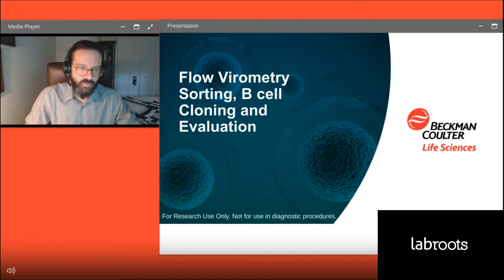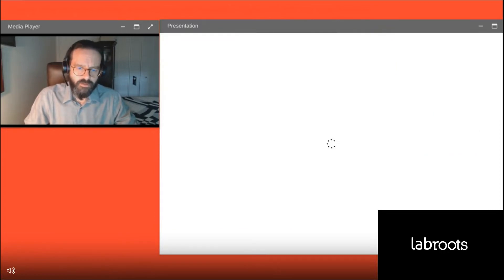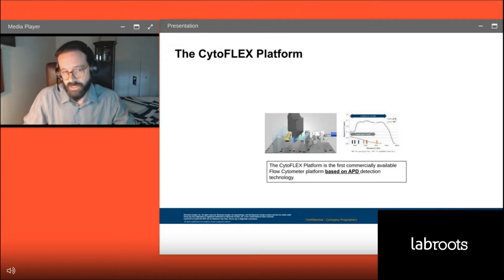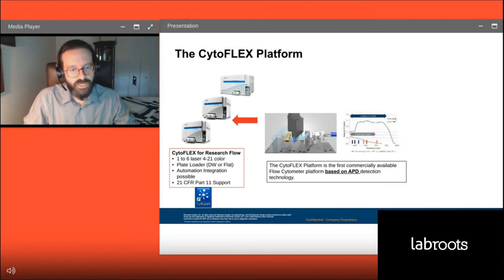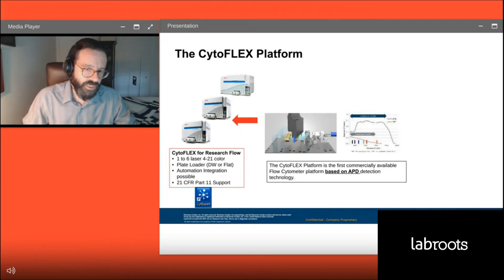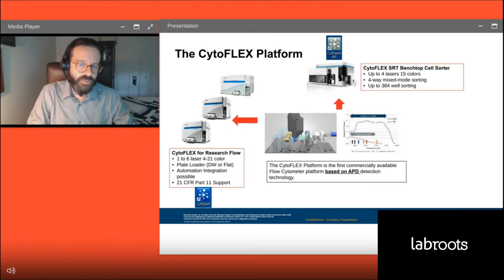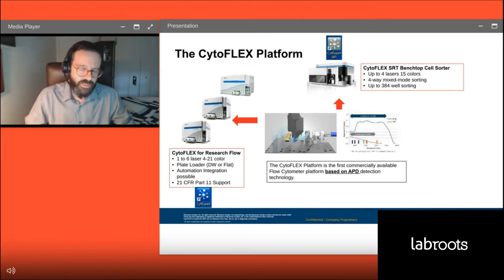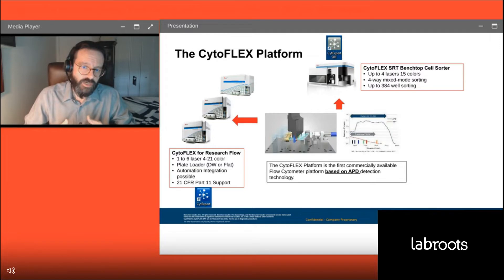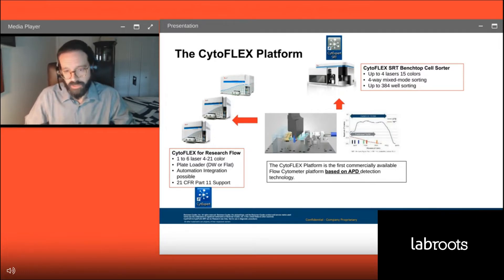I'd like to give a quick introduction to the CytoFLEX platform overall. The CytoFLEX platform is a commercially available flow cytometer platform based on APD detection technology — avalanche photodiodes — that are highly sensitive and very small in size, resulting in benchtop-sized instruments. We currently have three different models covering one to six lasers, up to 21-color detection, with automation integration possible and plate loaders. The next evolution was moving this into a cell sorting platform, trying to keep that small size and ease of operation.